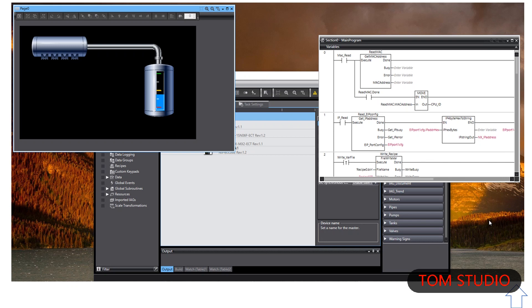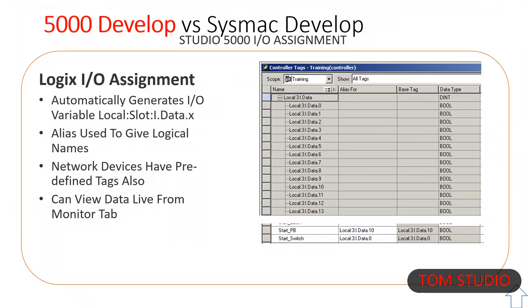Logix has canned tags for I/O that are not editable. Studio 5000 has an alias function to give them a logical name, added to a separate tag. The base tag is shown because you can alias an alias of an alias — giving multiple names to the same object can get confusing.